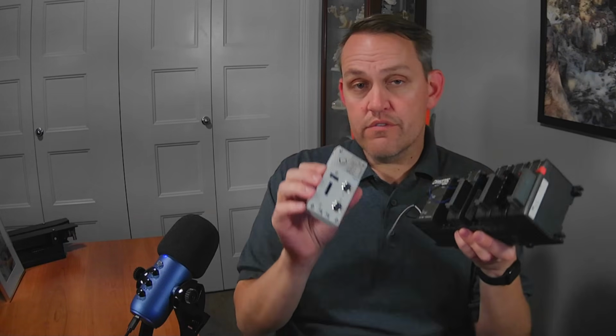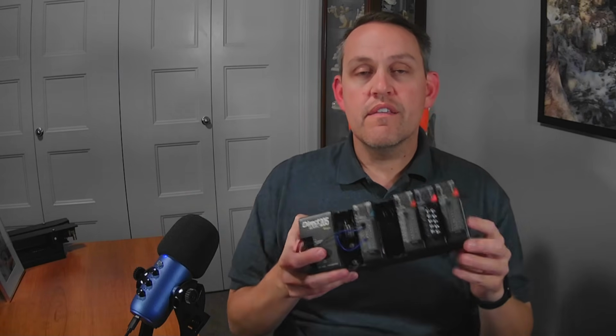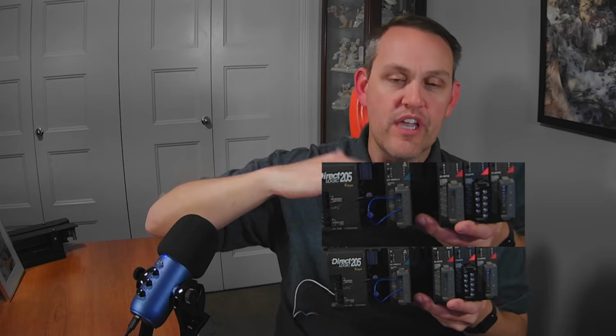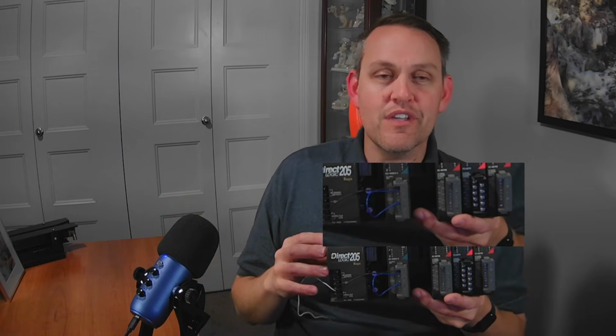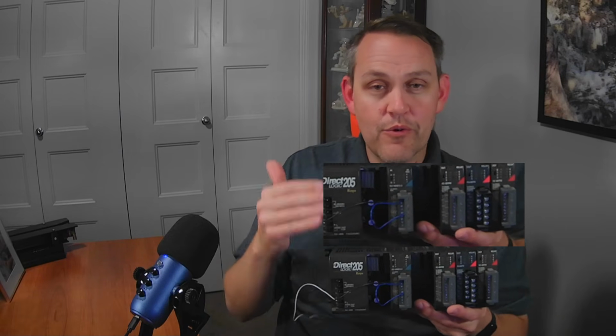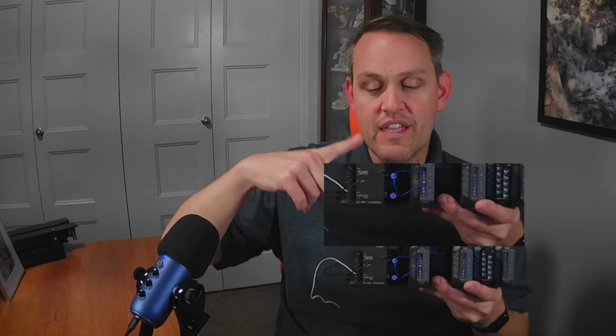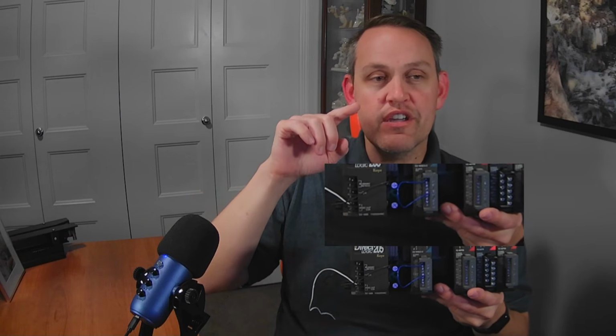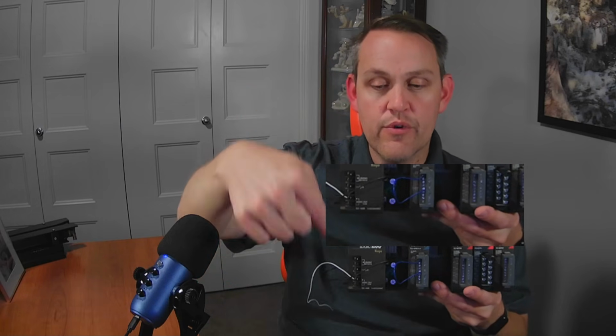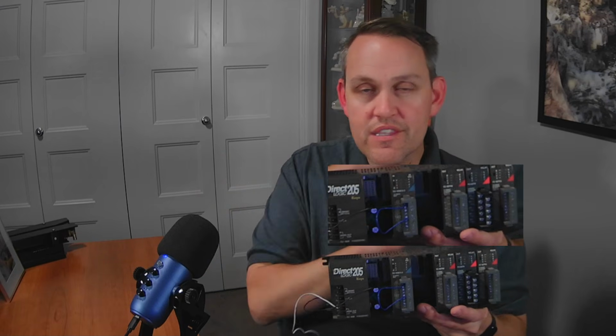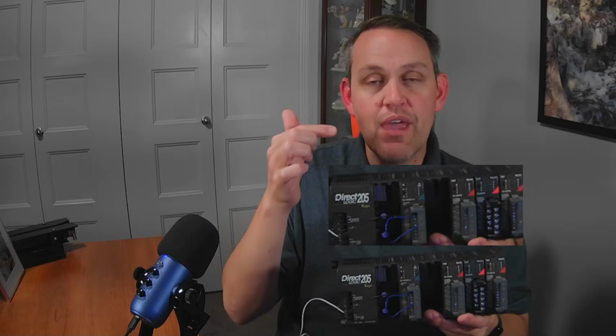We could flash forward from that. That was a two-step system. They've taken the main PLC, and now they've duplicated it into two. Now you have an A and a B channel. So the A channel is your main, your B channel is your safety essentially. They're identical PLCs, but they have two different strains of logic on the inside, to where the A PLC is pushing its entire memory out and it goes into the B PLC. And the B PLC does the same exact thing. It pushes its entire memory. It takes a photo of all of its I/O every tenth of a second, hundredth of a second, and pushes it to the main A PLC.